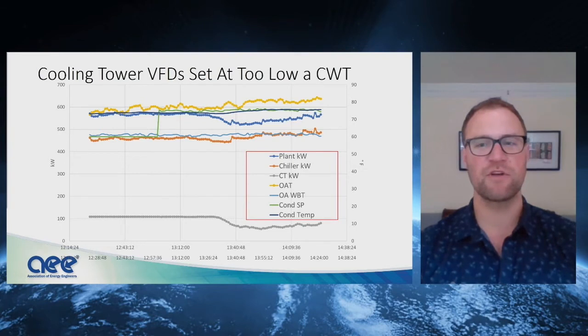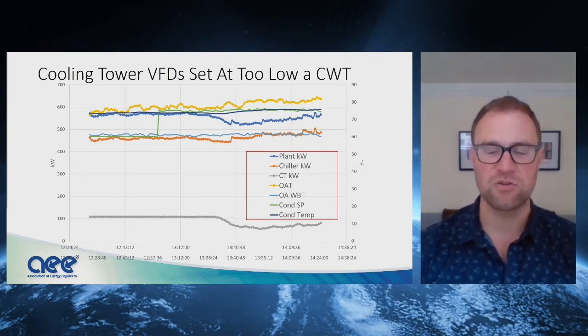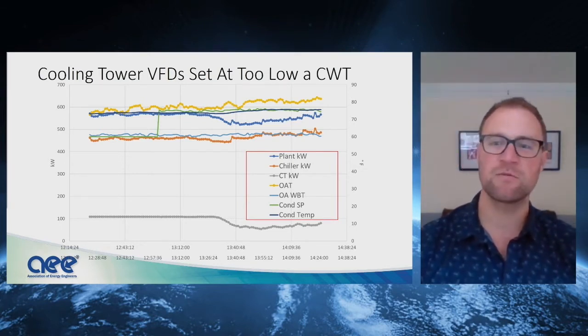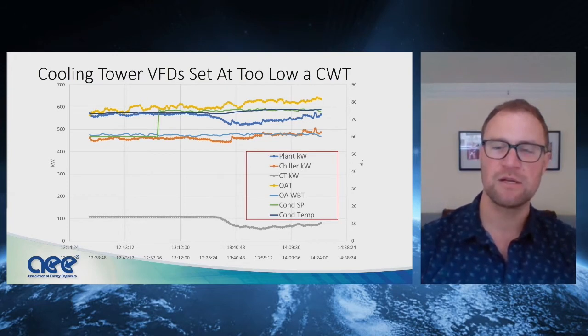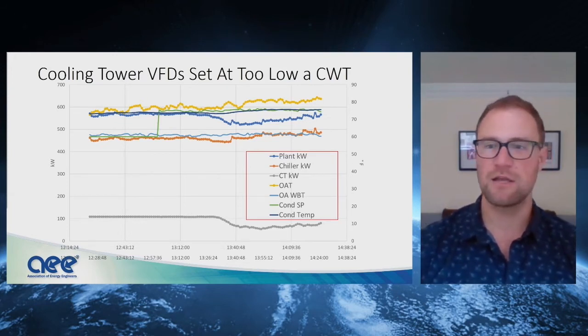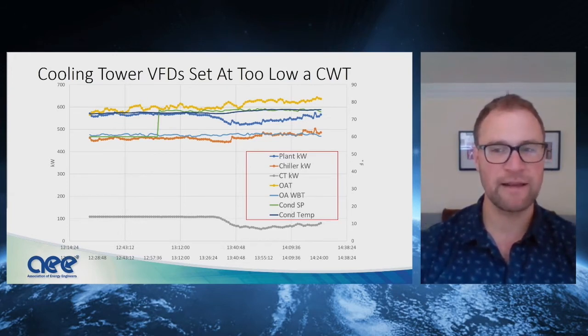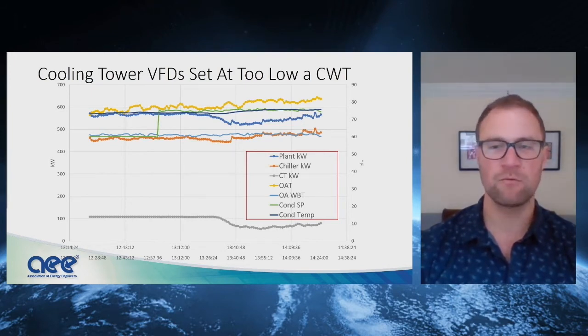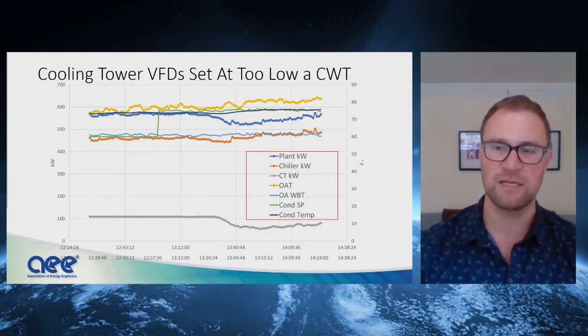So the general school of thought for chilled water plants is that you should drive down your condenser water temperature as low as possible to save energy at the chiller. It may cost you a little cooling tower fan energy, but the chiller is such a big user of energy that it's worth it. And while that's true to an extent, every system's different and the devil is in the details. So we need data to drive our decisions.